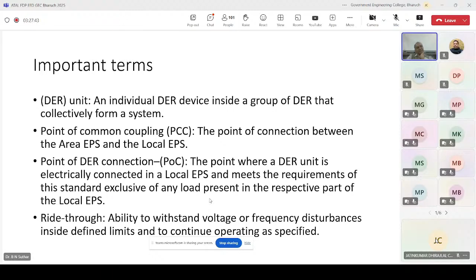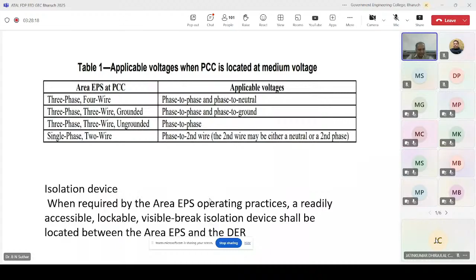And when we talk about the voltages which we need to measure at the PCC connections, as per the standards, if you have a 3-phase 4-wire supply, you have to measure the phase to phase and phase to neutral voltages. You have to take both. If you have a 3-phase 3-wire grounded system, you have to take the phase to ground and phase to phase. If you have a 3-phase 3-wire supply, then it's only phase to phase. And if you have a single phase or 2-wire system, it is phase to phase or phase to neutral.